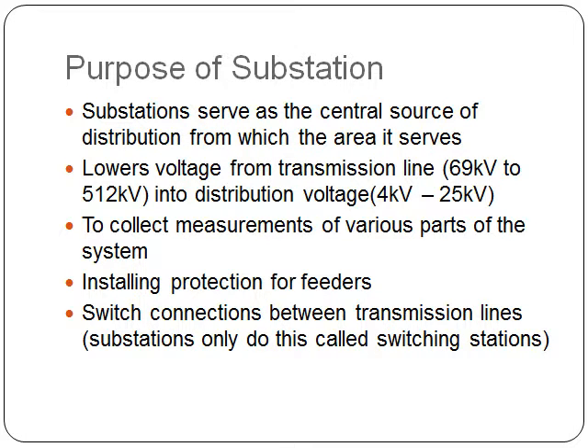Substations generally serve as the central source of distribution for the area they serve. A substation lowers voltage from the transmission line, which is usually from 69 kV to 512 kV, into distribution voltage, which ranges from 4 kV to 25 kV.